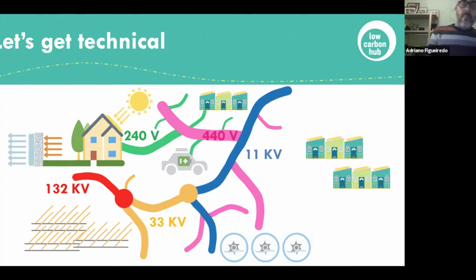So if we want to get slightly more technical, the national grid, the transmission network, the great big pylons, run at extra high voltage, 400 kilovolts. As they come into the bulk supply point, it drops to 132 kilovolts. From there, it goes into the primary substations at 33 kV. From there, it drops to 11 kV for each feeder. For every transformer coming out of that feeder, you have three phases that run at 440 volts. And then as it comes into our house, we receive it, for most of us, at 240 volts.